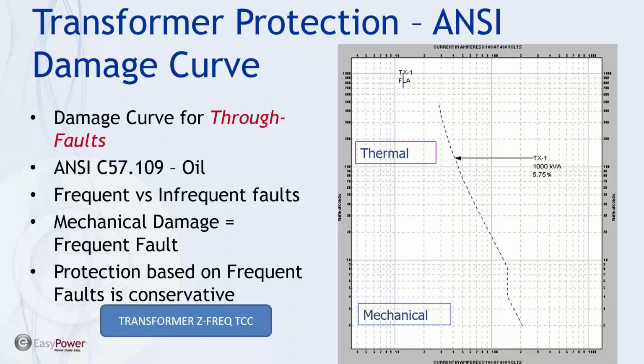The upper part of the curve is referred to as the thermal damage section, and we'll see where that's indicated in the plot. And then the mechanical damage section is at the higher current range, and it's offset from the 100% damage curve. So again, we're protecting at lower currents and longer time exposure from thermal damage, and at higher current for shorter time we're avoiding mechanical damage. So we're going to go into EasyPower here, and I'm going to show you where this is set up. But protection based on the frequent faults is conservative, and let's show where that's coming from.